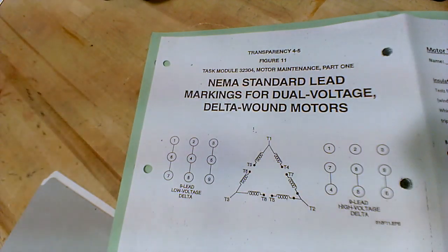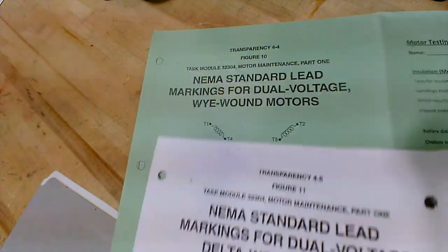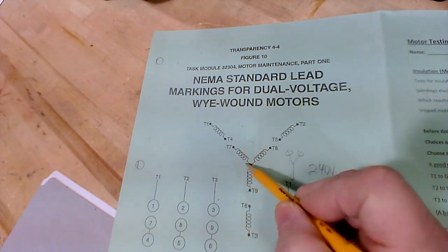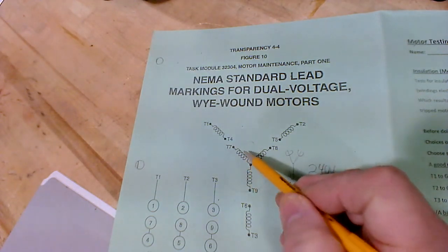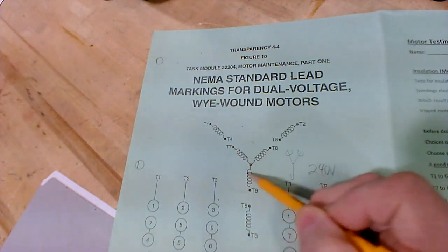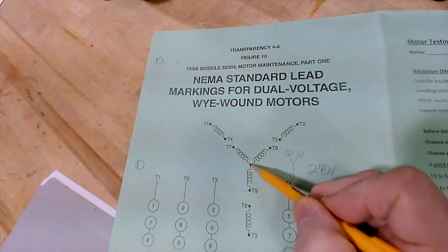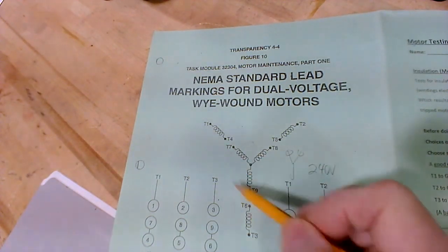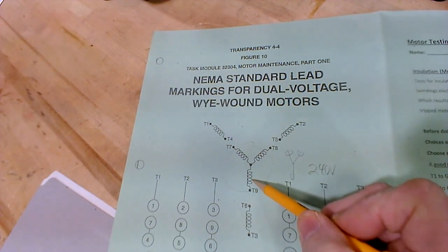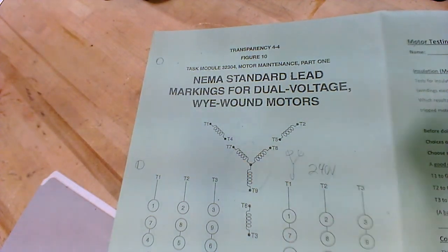Okay, and the difference between the delta and the Y is this. In the Y, embedded in the center of it, you have a permanent connection of 3 windings that you can't interrupt, a fixed connection in the heart of the motor that actually makes it a Y wound motor. There's a Y built into it in the heart of that motor. You can't change it. You can't make it something else.